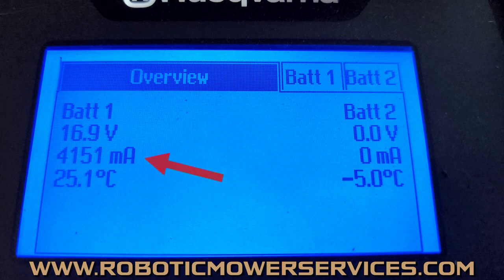You can either look at the overview, or you can actually go into battery one. You can see here on the overview that 4,151 milliamp, that is your charge current. Again, it's supposed to be at least 80% of the 4,200 milliamp. So we are well within that 80%.